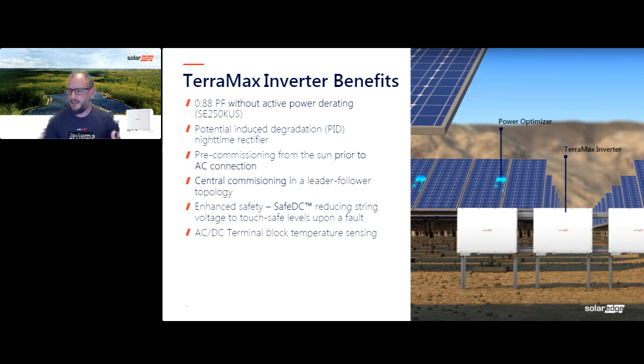Next one is AC and DC terminal block temperature sensing. We have temperature sensors built into all of our terminations on the DC and AC side, basically all the high current terminations where there could be the potential for a cable fault. Either a lug didn't get crimped properly, so you don't have the copper touching the lug properly and it's heating up because of the resistance. Or the lug wasn't torqued properly onto the termination itself, which again causes resistance to build up, and that generates heat.